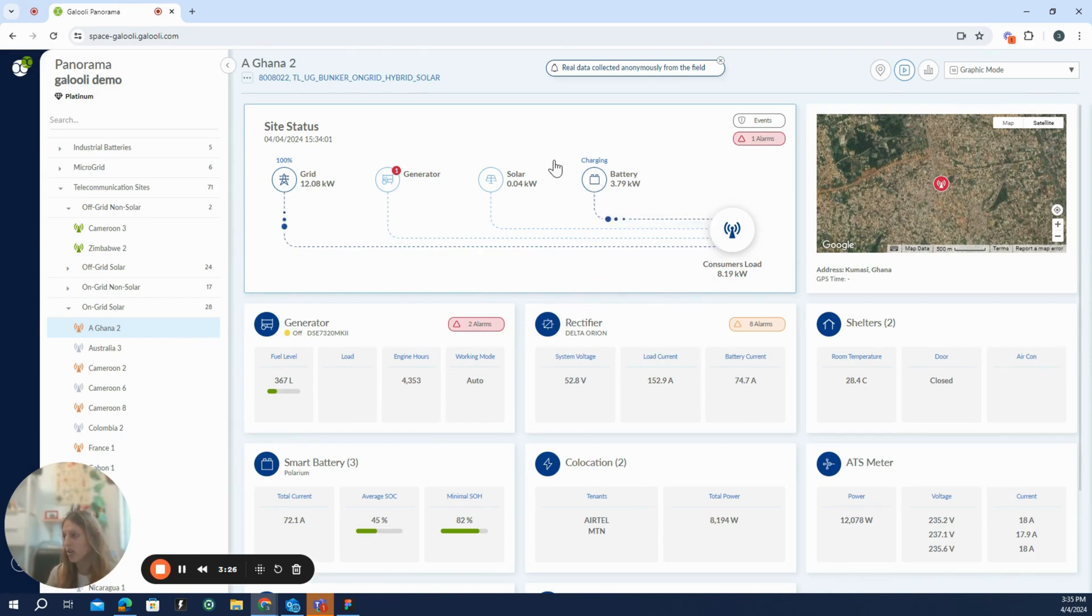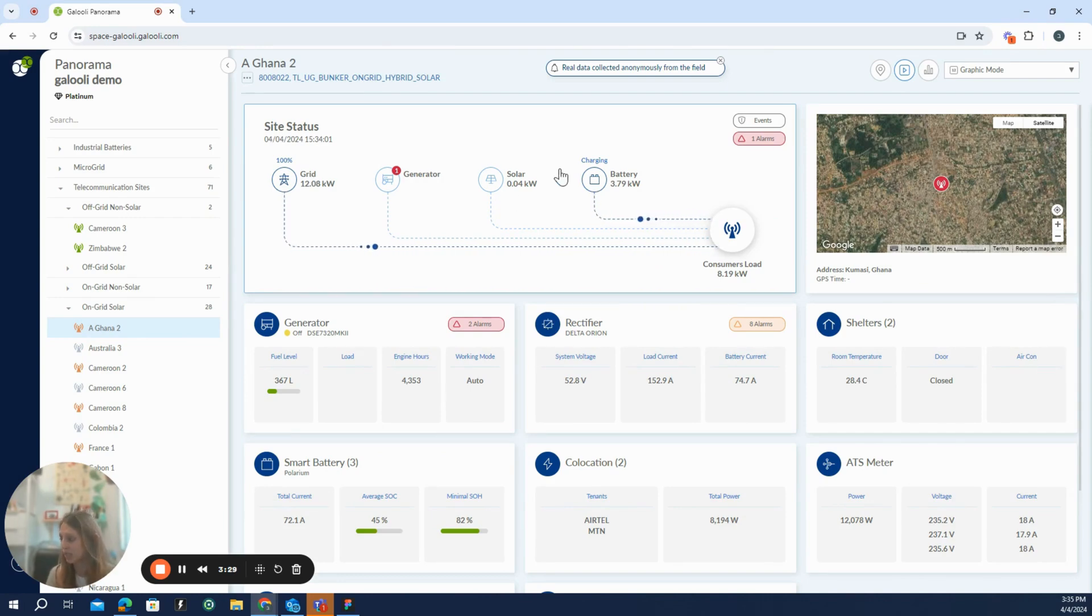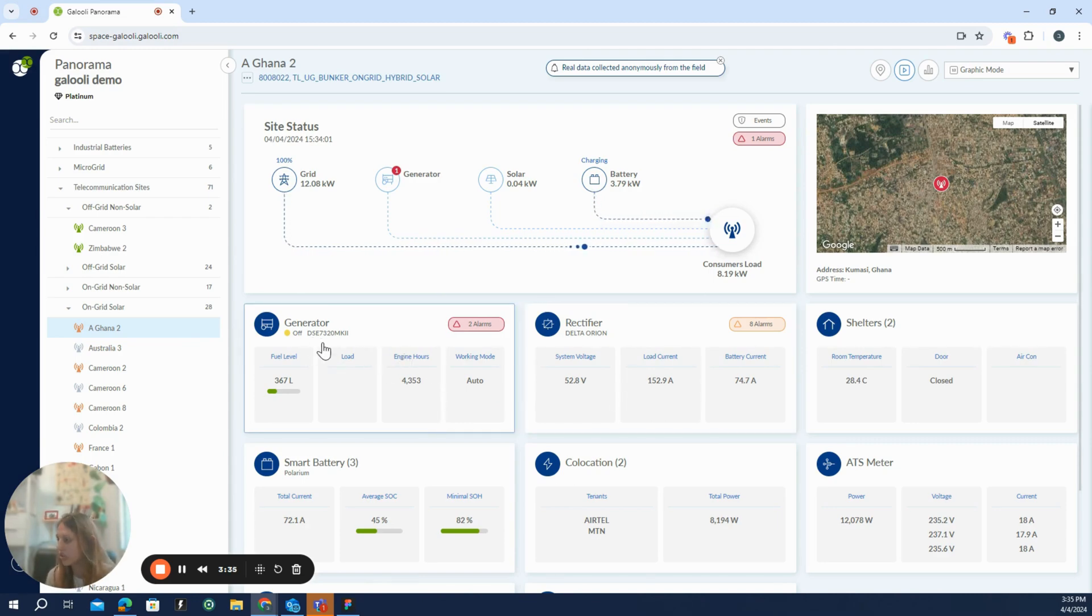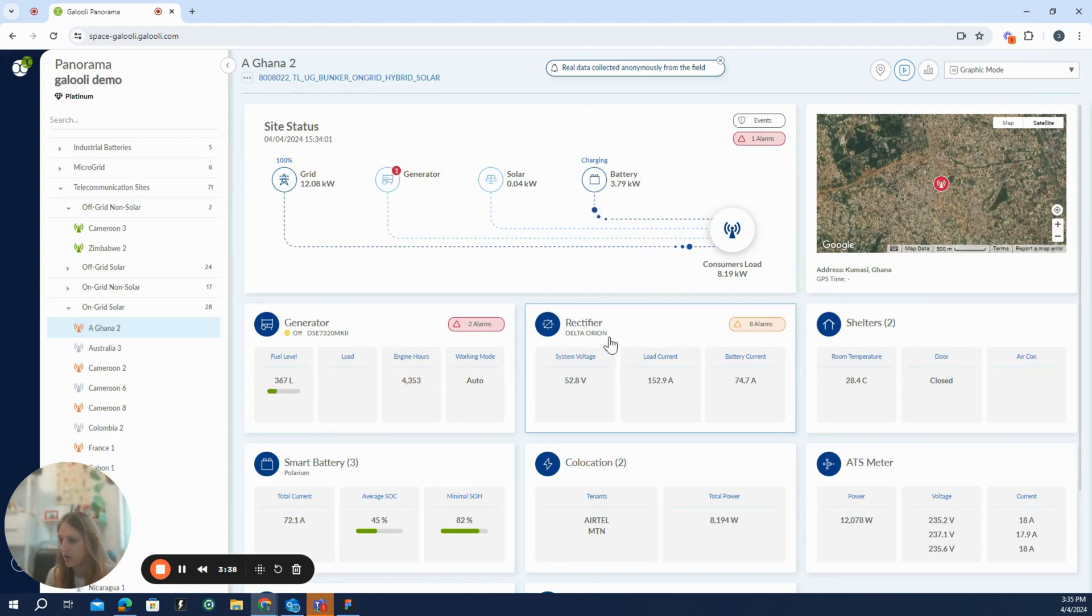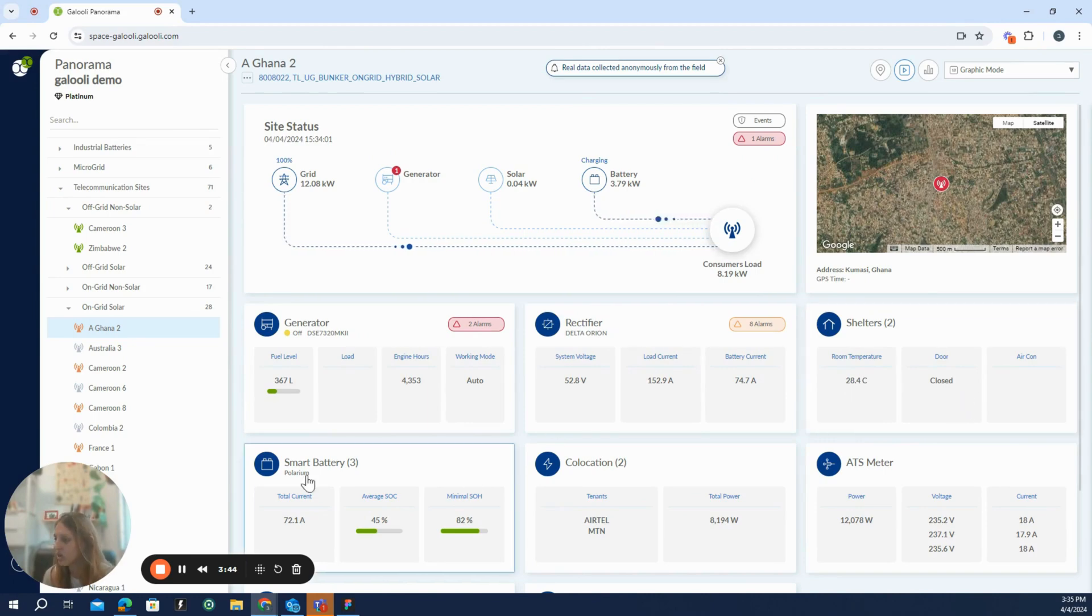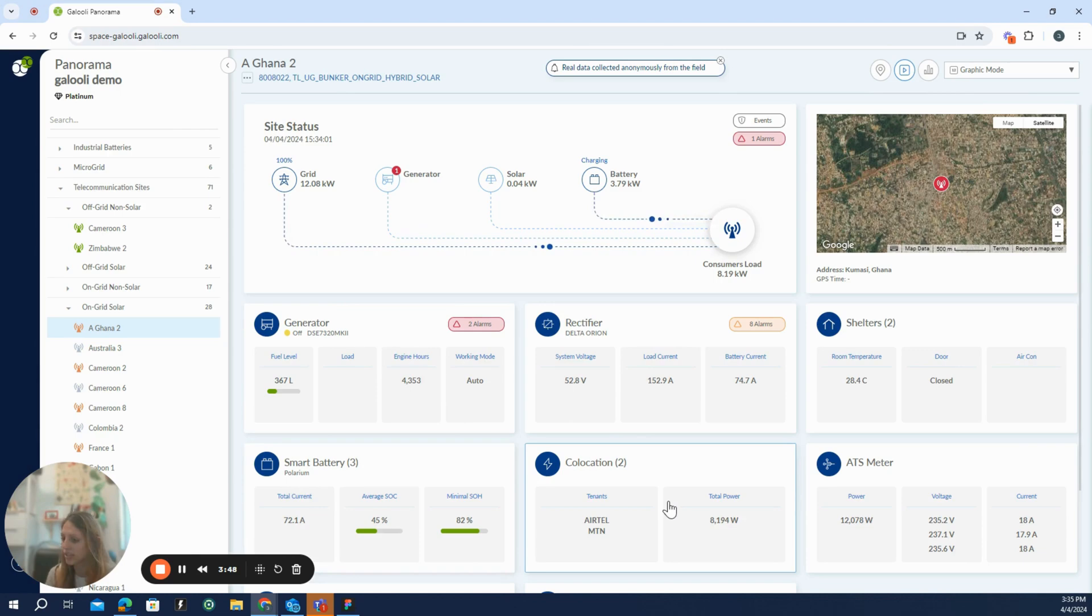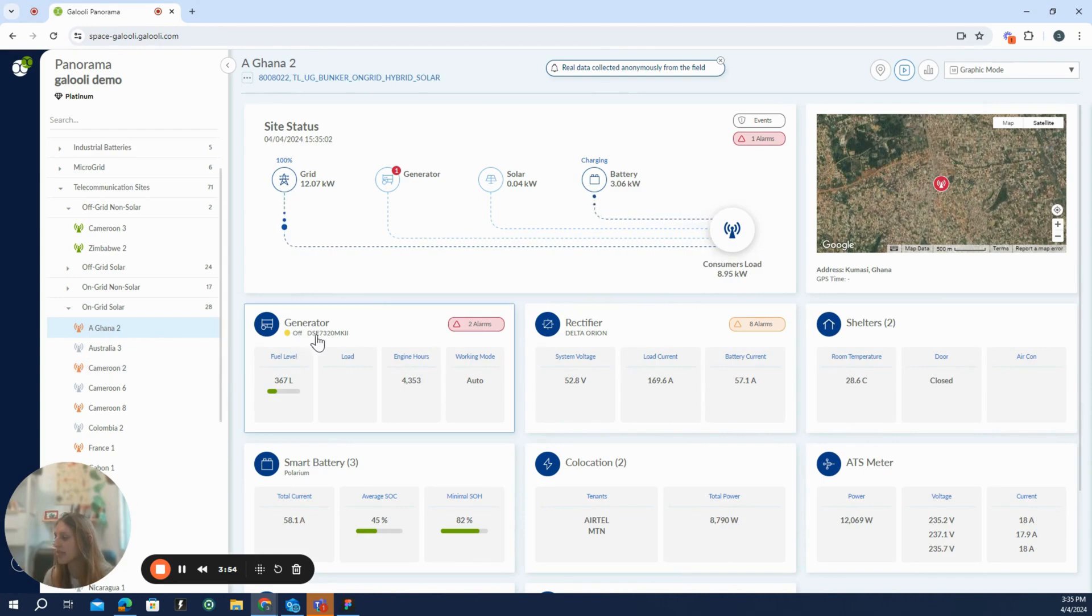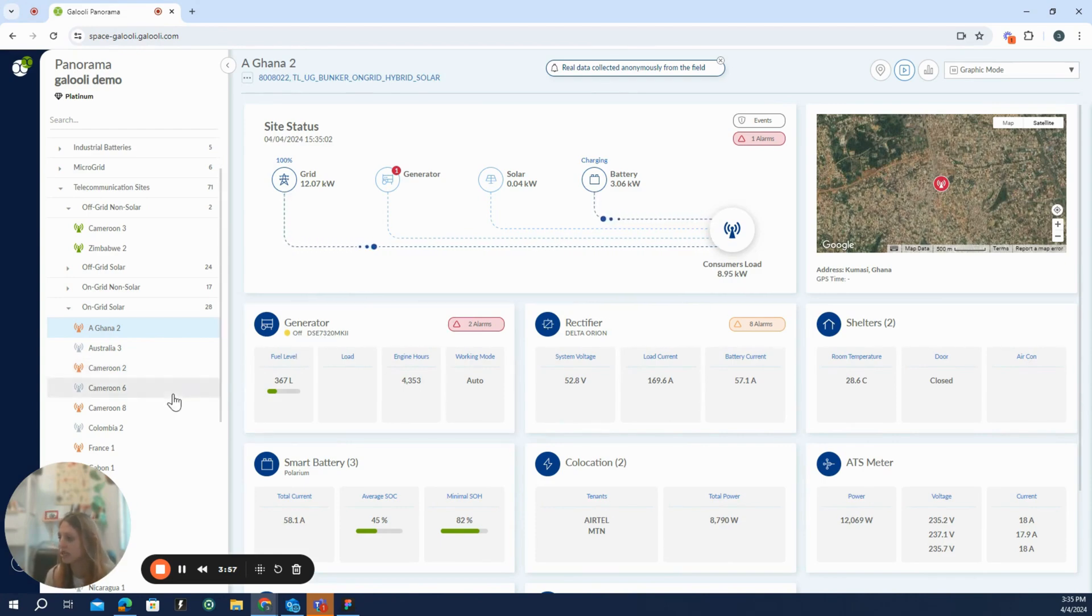As we saw very clearly what is going on generally in this site, we can see here the specific devices which are connected. So we have here a generator with a DeepSea controller, a rectifier with a Delta Orion panel, two shelters where we monitor the room temperature and the door status. We have three batteries from type Polarium, two tenants, and also an ATS meter.